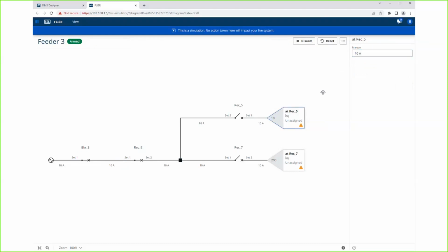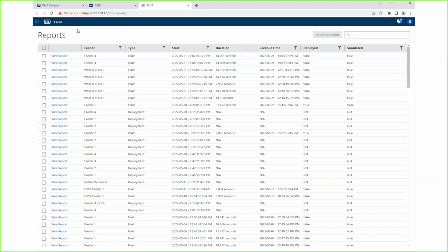So again, I can set a capacity limit here. So at rec 5, whatever feeder is on the other side of that only has 10 amps to give me due to heavy loading. And we should be able to quickly see what effect that has on FLISR. So the fault is in the same place, but there's 30 amps to pick up right there, and it won't be able to do that. So it'll go to the next available source, which is that adjacent one at the bottom. It's called @rec 7. So you can see rec 7 was closed instead of rec 5. The only thing I changed was the availability of those adjacent circuits.